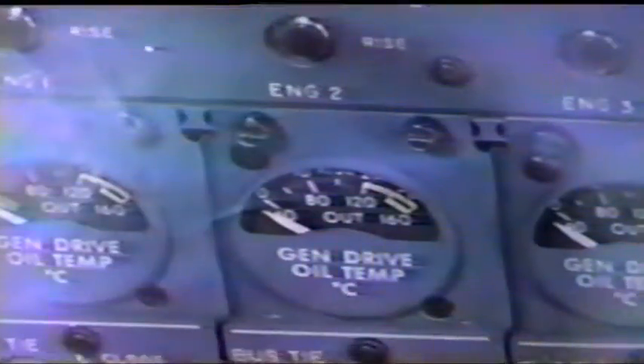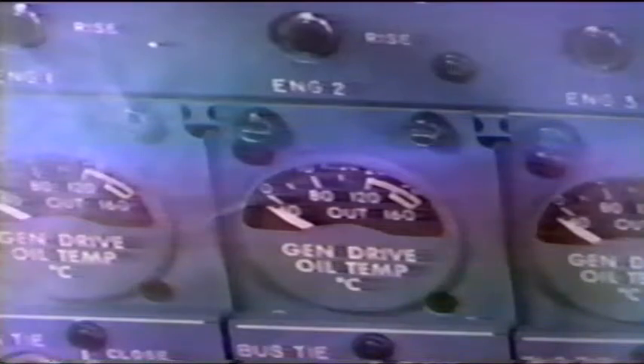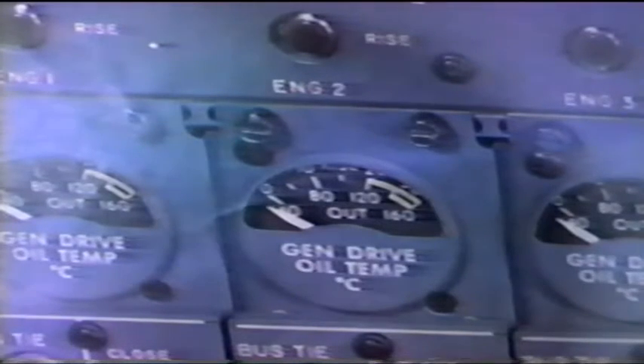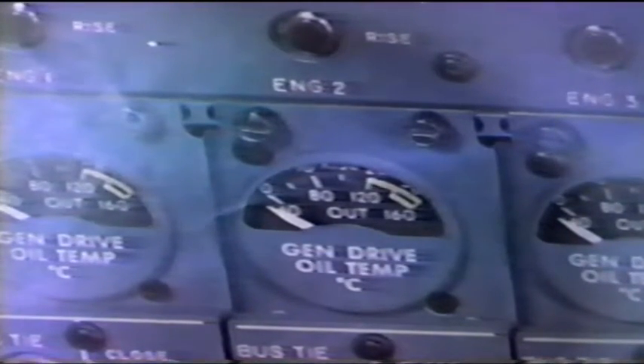You'll notice now that we have a button here that says rise, and some airplanes have a toggle switch. When we press the button, instead of reading the generator CSD temperature leaving the CSD, the out temperature, we get a measure of how much the temperature has risen going through the CSD. That is, we're really measuring the in and the out temperatures, and we're comparing the two. Now, you can see that this temperature gauge is labeled rise on the upper scale and out on the lower scale, and we've got a button that we press for rise.